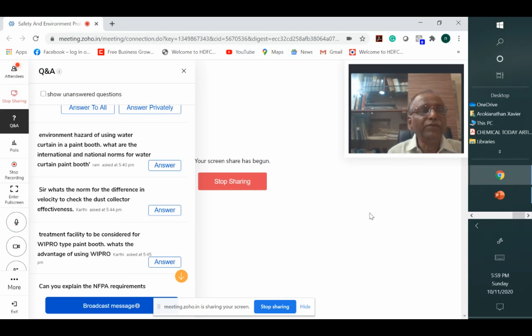I'll tell you one thing, sir. Take powder coating. People want to do powder coating because it's very economical. They just buy the powder, spray it, and open up, and the full plant becomes full of dust. The cost of powder is about 150-200 rupees a kg. I had to convince the customer that all his money was going down the drain. He didn't understand, because in powder coating there may be only 30 to 50 or 60 percent transfer efficiency, and the remaining 30-40% is overspray. Now if you have a cyclone recovery unit, you can recover that powder and recycle and reuse it, so you're saving cost. When I explained this clearly with data, I said you will recover the cost of the dust collector within 3-4 months depending on usage of the powder. Immediately he was convinced and got a recovery unit.